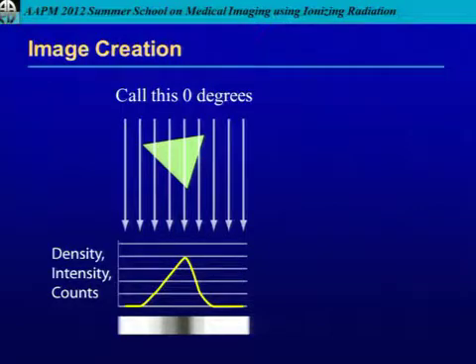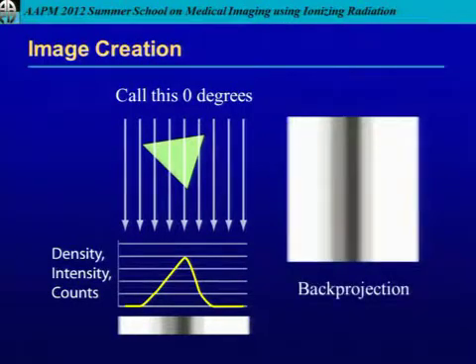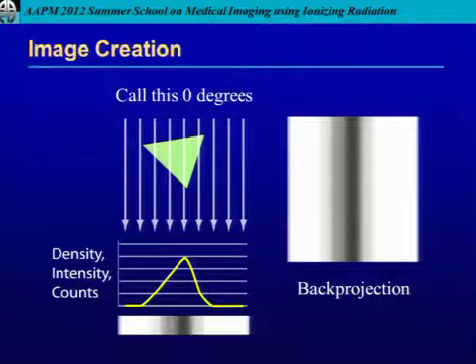To create our image from only that one projection — that's all we know — our image would look like that one-dimensional strip. You hear this referred to as smearing the data back, but it's really just the data set covering the entire field of view. This is called back projection.